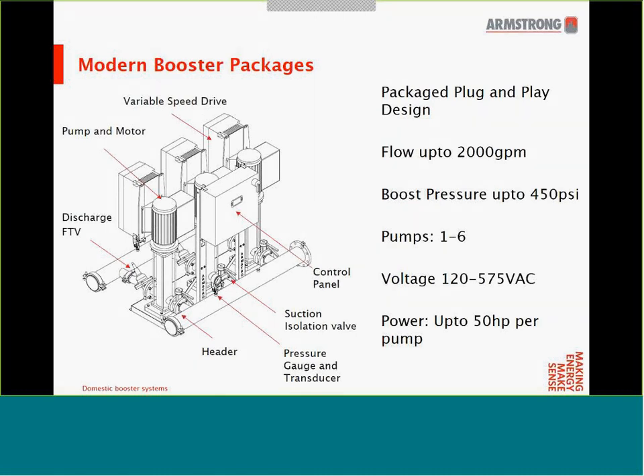Now let's look at a modern booster package. Unlike in the past where individual components needed to be selected and installed on-site, modern booster packages are designed such that all components are built at the factory and easily commissioned on-site — making the booster package a plug-and-play device. Typical booster packages include pumps, motors, and variable speed drives, allowing us to control the flow according to building demand. In most modern booster packages, all the pumps are identical. This diagram shows a triplex, which is a three-pump system with each pump and motor identical.